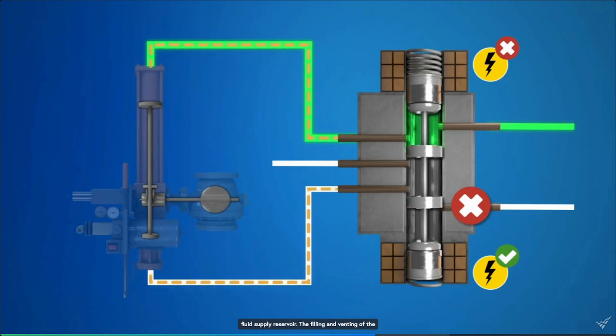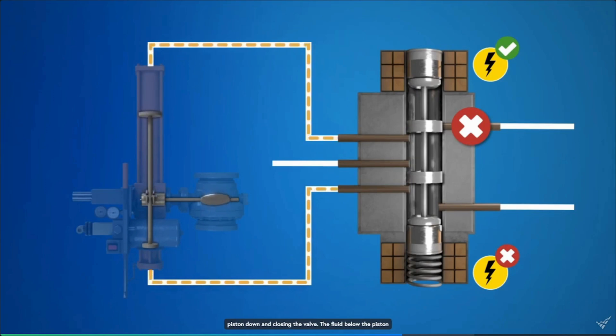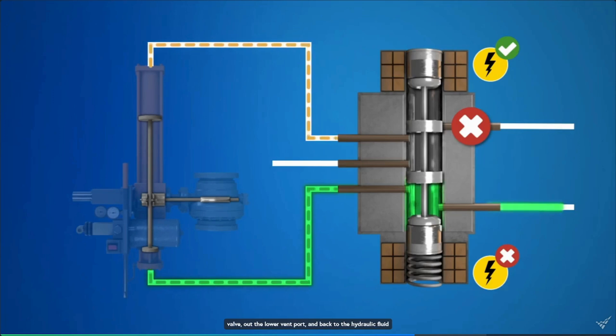The filling and venting of the actuator's cylinder are reversed by de-energizing the lower solenoid and energizing the upper solenoid. When the upper solenoid is energized, it pulls the spool up, blocking the upper vent ports and lower supply ports. Hydraulic fluid is supplied to the top of the actuator's cylinder, pushing the piston down and closing the valve. The fluid below the piston is vented through the lower fluid line, back through the pilot valve, out the lower vent port, and back to the hydraulic fluid supply reservoir.